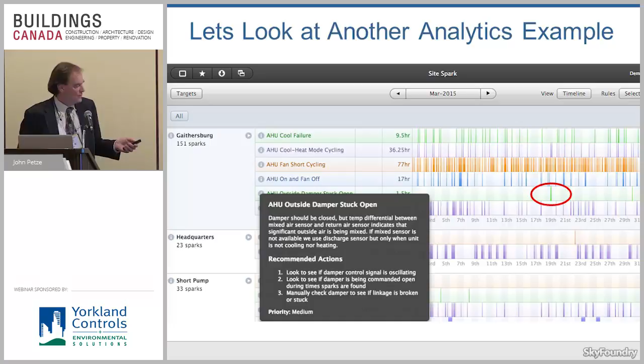But we're looking at a monthly view. If I clicked, it would take me down to more detail. Here now we're looking at that specific day, Thursday the 19th of March, and now I can see the patterns much clearer. And here's my rule, and here's my duration, and here's the time. I think it says 6:32 p.m., and I can see that I had a period of time that condition was true, and then it stopped, the white space, and it came back again. So it happened twice. But what else does this visualization approach make really obvious? Correlation, right? You don't need to know a lot to go, hey, these two things are happening at the same time. What is that? Oh, that happens to be short cycling between heating and cooling on the unit. Aha. Maybe that's the root cause of this problem, right?